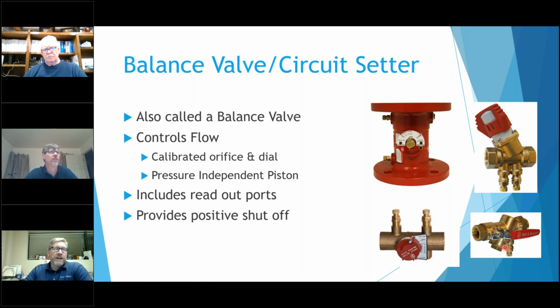This is not adjustable. A lot of people like these in a variety of systems, because you cannot go in there and, when someone says, my little area is too cold, so I'm going to go open this valve up. No wonder, if you had a circuit setter, oh, no wonder it's only 20% open, and they don't realize that when you open this up, you might get a little more heat, but now somebody is losing heat, and you can have bigger system-wide issues. But with this valve, it cannot be adjusted. So, no matter what they try to do, it just isn't going to give you any more flow. You can certainly do less flow. You can certainly come in here and change the cartridge out to a different flow that you need, but it's just not as easily done as with the dial.